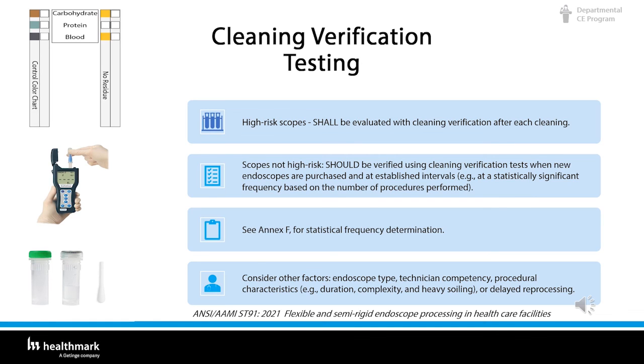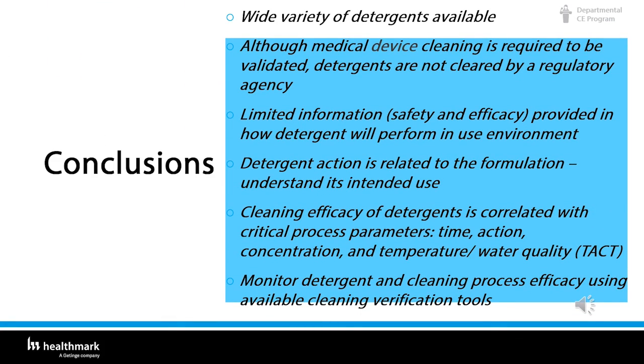Here are the conclusions from today. One: there is a wide variety of detergents available. Two: although medical device cleaning is required to be validated — detergents are not cleared by a regulatory agency. Three: we have limited information on the safety, efficacy, and how a detergent will perform in its use environment. Four: detergent action is related to the formulation — understand its intended use, whether for blood or grease. Five: cleaning efficacy of detergents is correlated with the critical process parameters — TACT: time, action, concentration, temperature, and water quality. Lastly: monitor detergent and cleaning process efficacy using available cleaning verification tools.